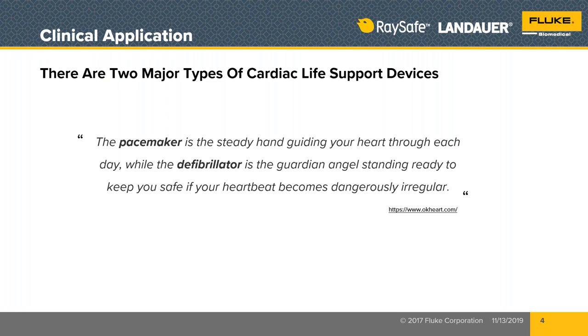All temporary pacemakers are designed to detect the lack of a heartbeat. And typically you don't pace asystole, which is a flat line, meaning no heart rate. You don't pace them. What you pace is slow heart rates. So there is a heart rate there. The reason that the pacemaker is designed to not try and pace asystole or flatline is it needs to alarm and call out asystole or flatline, because either the patient is dead or we need to do something else besides pacing in order to get the heart to start beating again. These are not just instrument only devices.